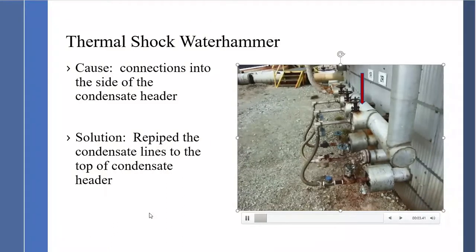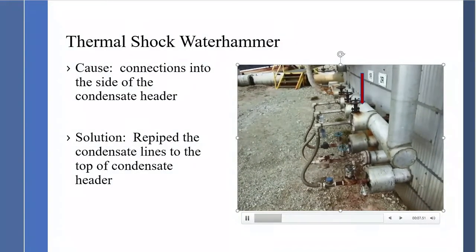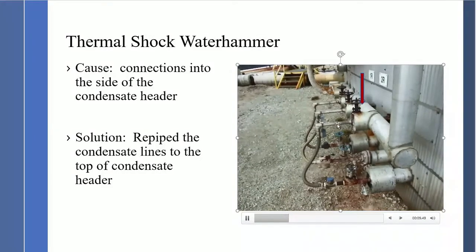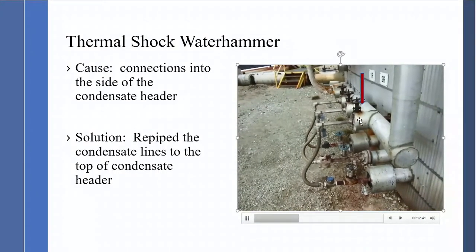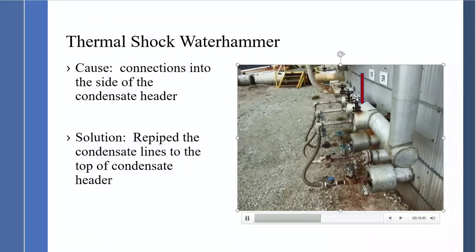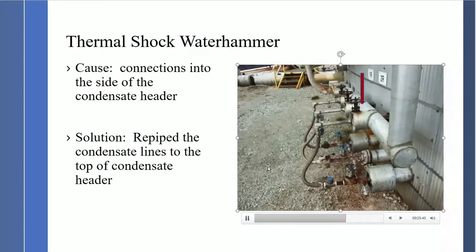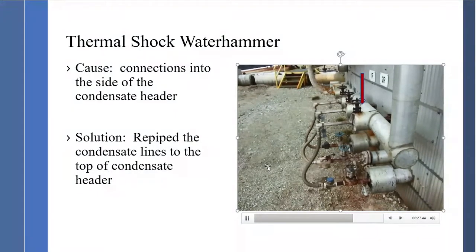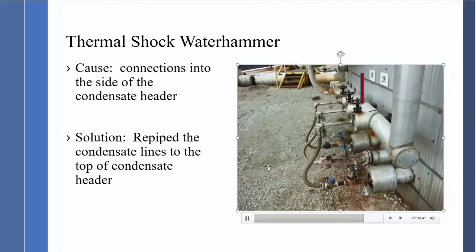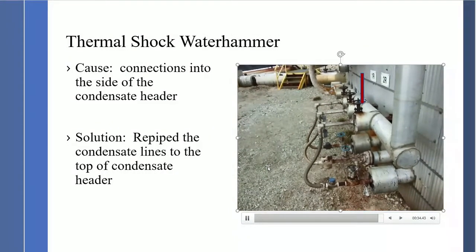You can hear the noise and see the movement in the pipe because it is connected into the side of the header. The solution is very simple: re-pipe back into the top of the header and the water hammer will go away. They went through a variety of steam traps, piping, and flex hoses trying to resolve the water hammer, but piping to the top of the condensate header is what resolves it.